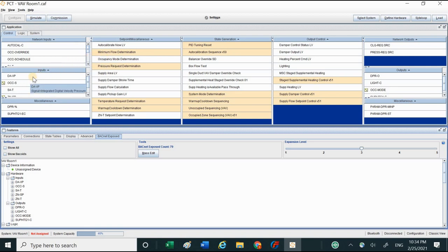And here, this is the supply air temperature. You can see the signal is nickel 1K RTD. This is one type of sensor. But the sensor we use in this system, in our lab, is a different type of RTD. So we need to do the setting for this sensor. So right click and modify the signal.